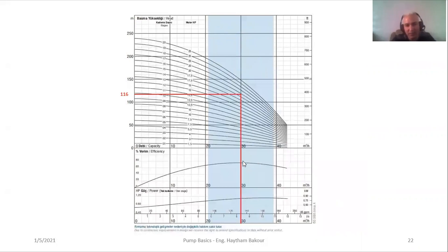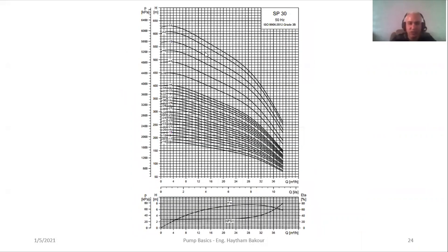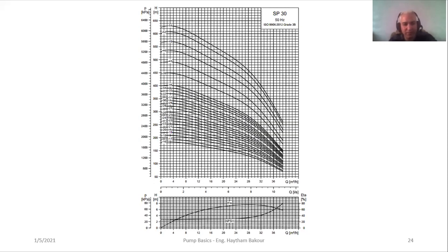From those curves we can see the value of the efficiency, the value of the RPMs, and the watt value. Now we are going to go to the Grundfos website. This chart currently is from the Grundfos catalogs. To do a manual search, I need to go through the pressure, find the flow rate first, go vertically, then find the head horizontally, and find the crossing point — but it is not really efficient or practical. So let's go to the website and find the easy way.